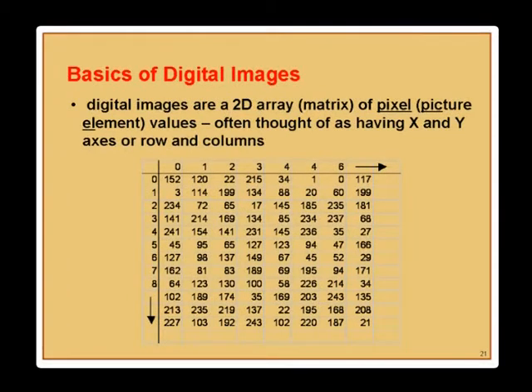Digital images are 2D arrays of pixel elements. In a chest exam, each pixel element could be about 127 to 200 microns, and similarly in fluoroscopy. In mammography, you look at smaller pixel elements — anywhere from 50 to 80 microns, sometimes 100 microns — because you are looking for microcalcifications that could be about 50 microns. You need appropriate spatial frequencies to visualize objects in different exams.